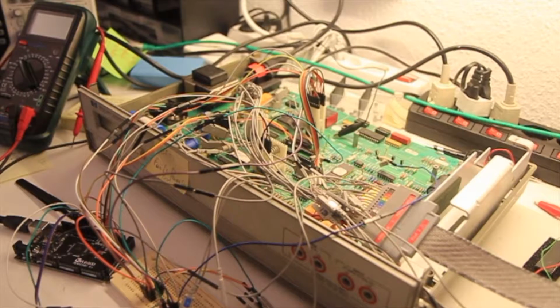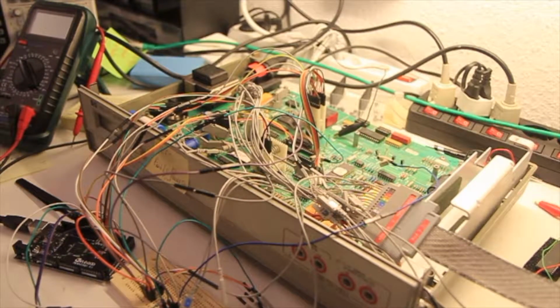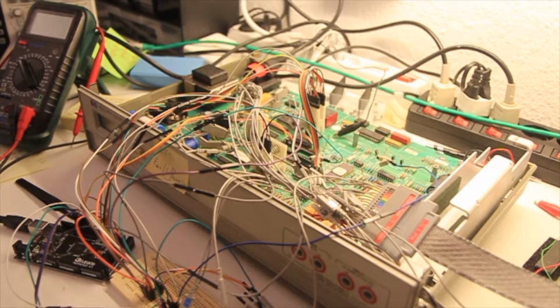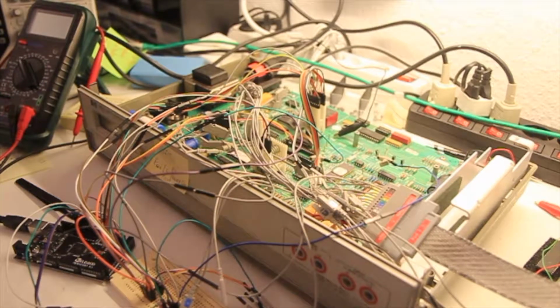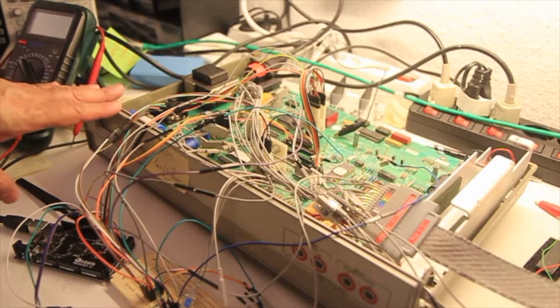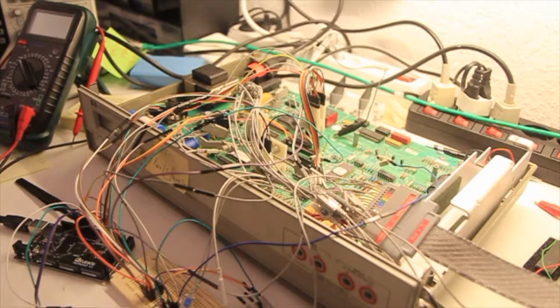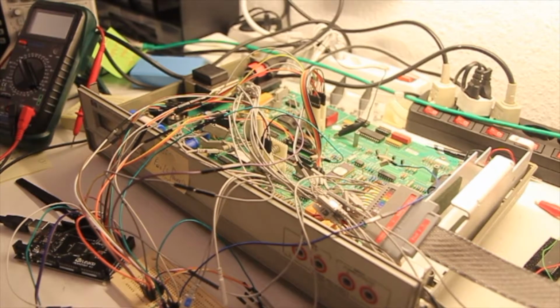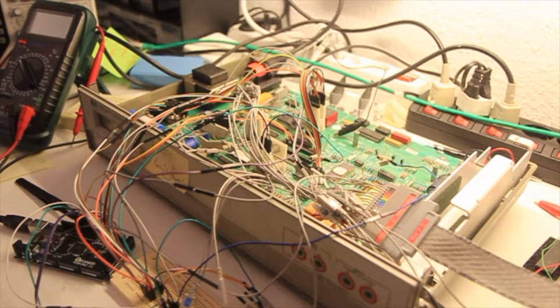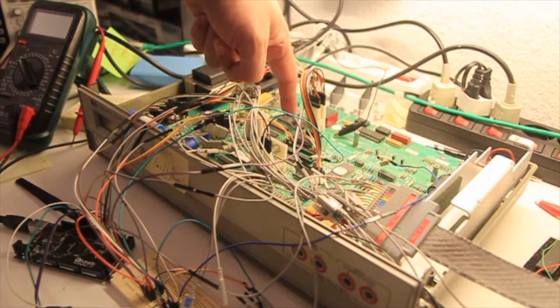Hi, here we are again looking at the 3421A data acquisition and control unit. The problem with this unit is that it does not power on. Essentially, when I apply power, you hear the first click, but nothing comes on the display, and you don't hear the second relay click. So I ran the diagnostics outlined in the service manual, and they suggested that the CPU was at fault.